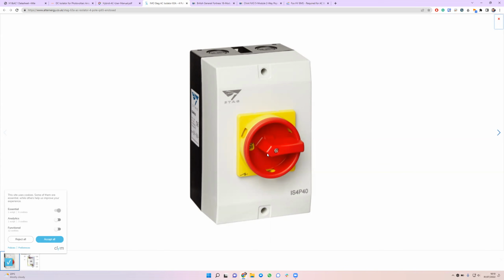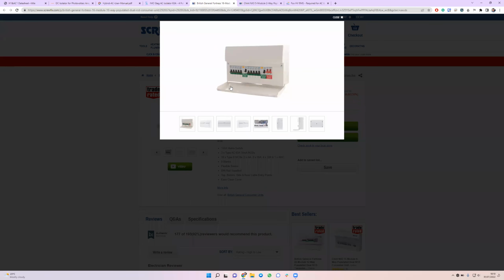And if you don't have one of these, although again, you should have one, it should be near your inverter, easily accessible. If you don't have one of these, you will probably find in your consumer unit or fuse board or switchboard, whatever you wish to call it, distribution board, they're all the same thing. You should have a marked circuit that says solar on it. You'll want to flip that switch to the off position, and that will isolate the solar as well.